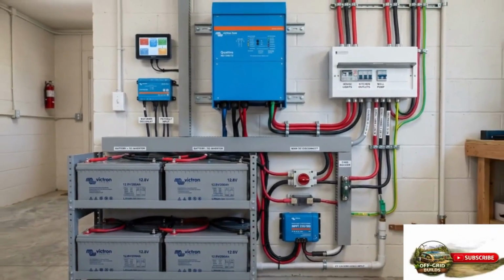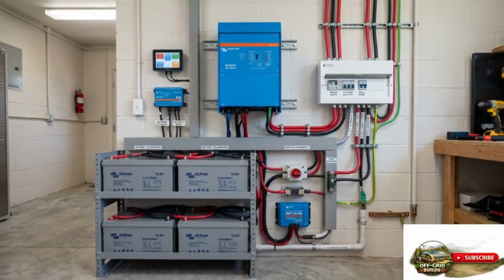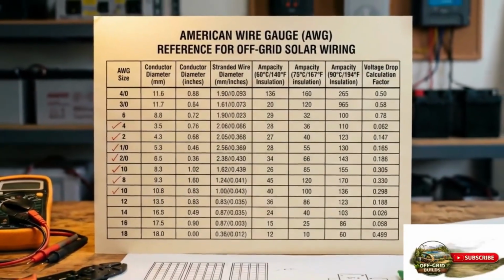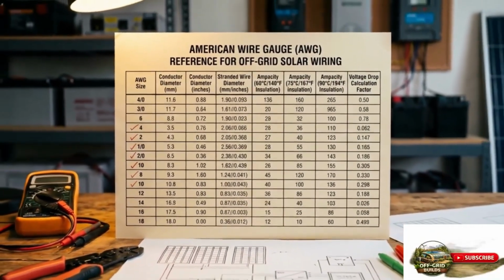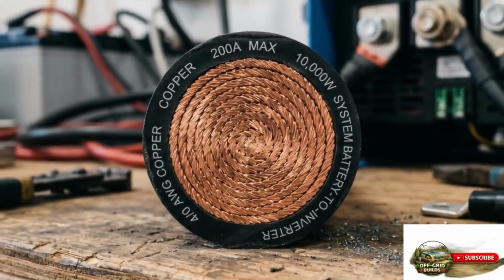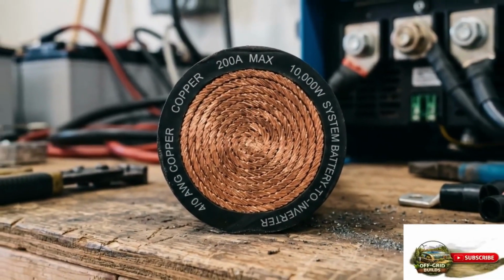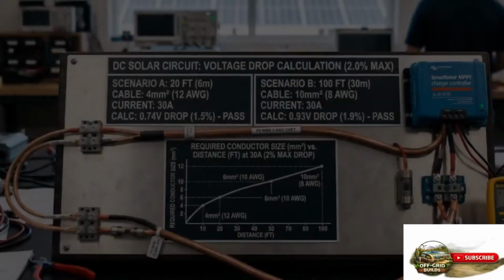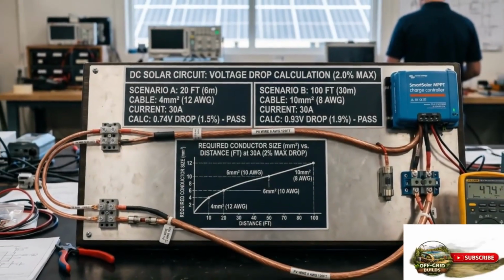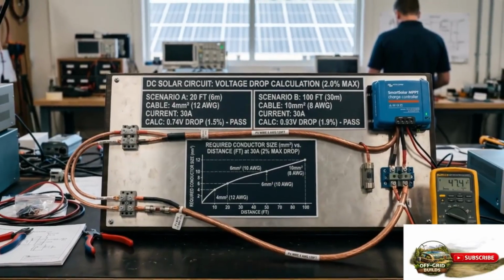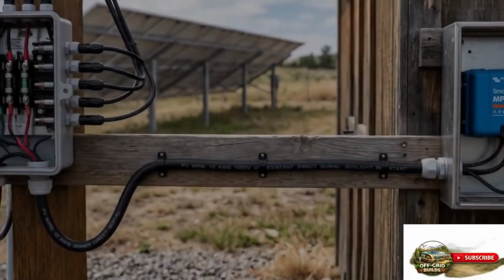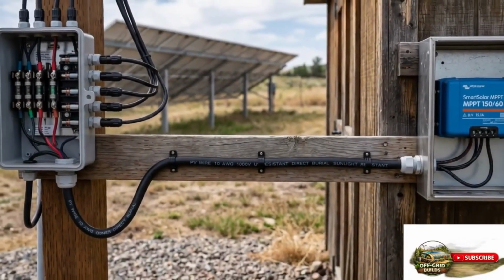System wiring. Sizing your conductors correctly. Wiring is not the glamorous part of solar system design, but it is where most system problems originate, in both performance and safety. Incorrectly sized wiring causes resistive losses that reduce system efficiency, voltage drops that cause equipment to behave erratically, and in severe cases can cause overheating that presents a fire risk.